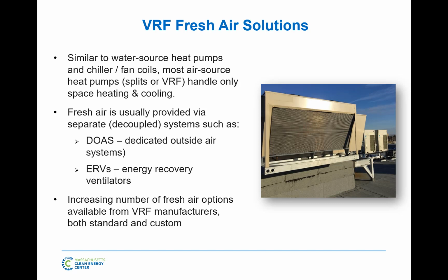The disadvantage is that it's very big. You can fit a wheel in a rooftop unit at 6 inches of length, whereas a core may be 6 feet of length. That's how big of a difference it might be in a 10,000 CFM unit. So DOAS units and ERVs can be one and the same. I'll go through some different options here.